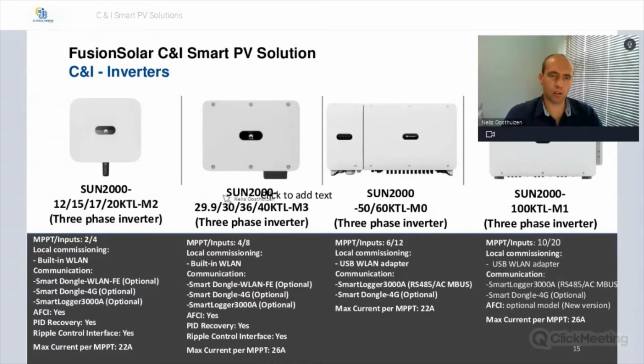AFCI is built in, PID Recovery is built in, and ripple control is also active on this segment of inverters. Then please note that on these sets of inverters, specifically the M3 range, the maximum current per MPPT has increased to 26 amps. So you will definitely be able to use 2 strings on 1 MPPT, and it will be safe for both the system as well as the inverter.